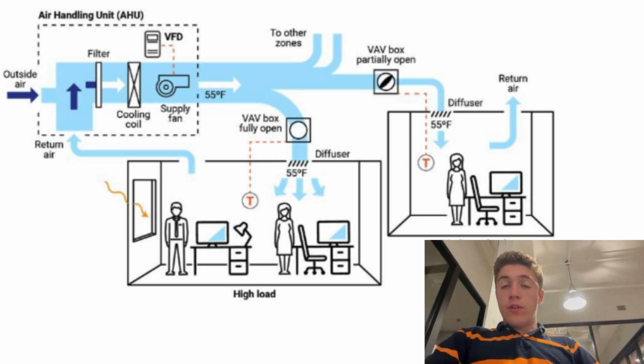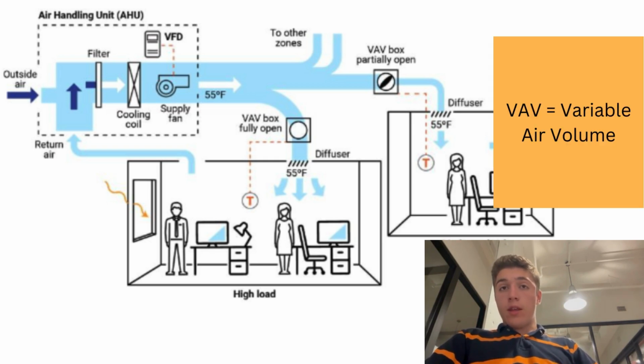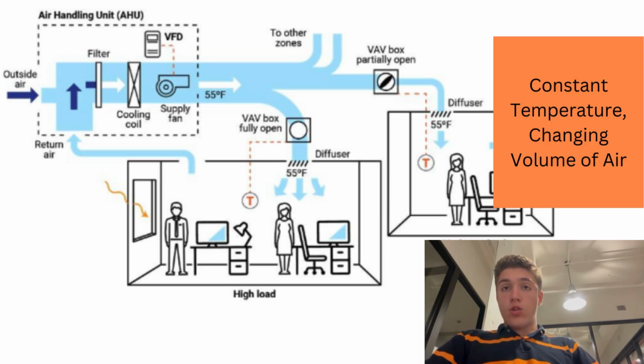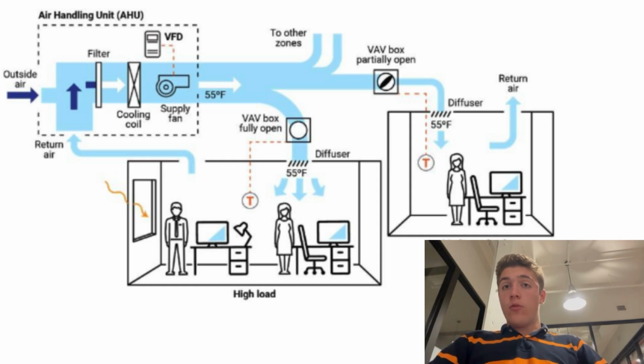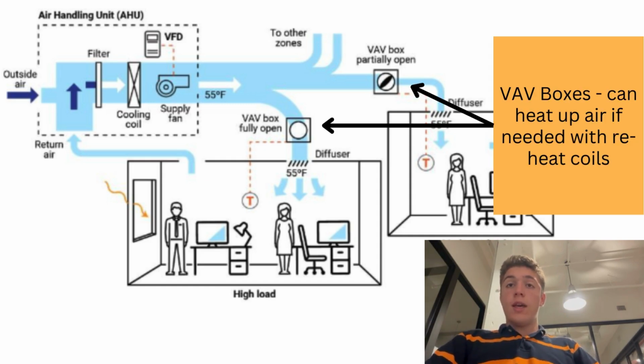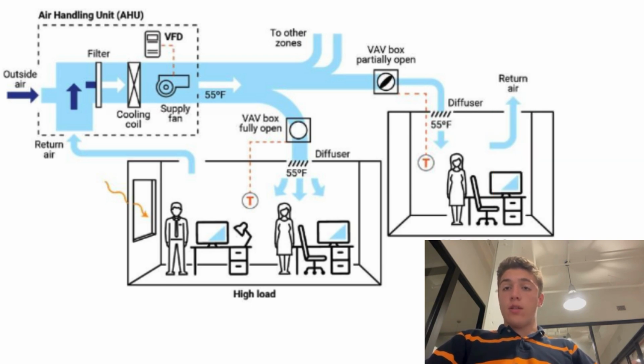Next, we're going to be using VAV boxes to distribute the air. I think this diagram does a great job of explaining what a VAV is and does. A VAV stands for variable air volume, which means that it can control the amount of air going into a room with an adjustable damper while keeping the air temperature constant. This leads to a very efficient way of air distribution because each room can have its temperature controlled individually and the air doesn't need to be cooled or heated to different temperatures. It just needs to be kept at a constant temperature.